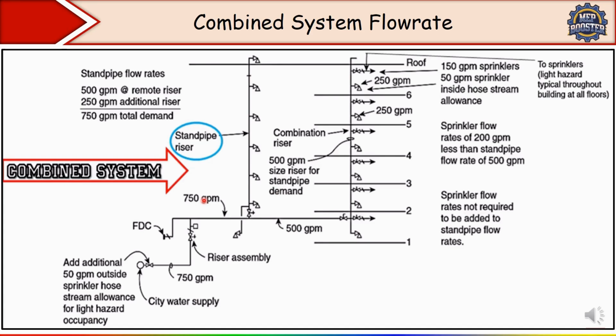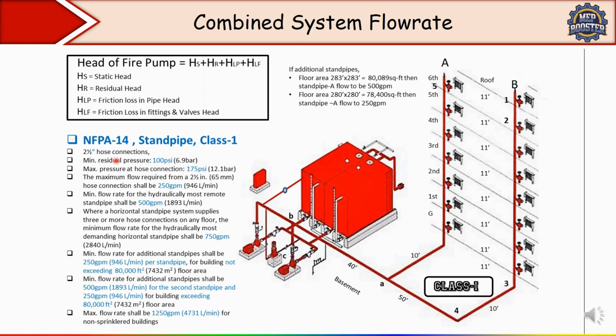So here what happened? As I told you, the combined system integrates both sprinklers for automatic fire suppression and standpipes for manual fire suppression via hoses. So if you see here, we have a sprinkler, and the standpipe, meaning the hose connection, is also given. All of you know that for the most remote standpipe there is a required flow rate. See here it is given clearly. If it is a Class I standpipe system, and the image which I have shown is normally a Class I standpipe, here we have a 2.5 inch hose connection. The minimum requirement is given for a Class I standpipe system: minimum residual pressure 100, maximum 175.